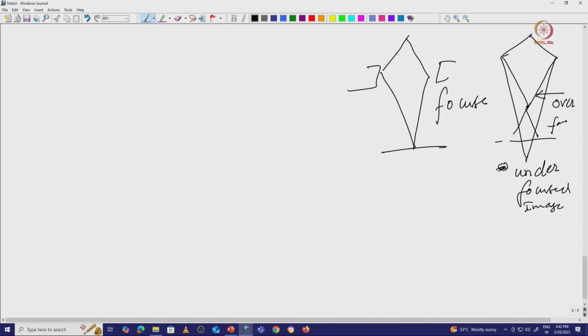So let us see, if we are using a different magnetic field, how it is going to affect. Whenever I talk about focusing the electron beam, especially after interacting with the sample, how it is focusing and how we are getting the first image in the back focal plane. The back focal plane is the plane where we are getting the diffraction pattern. In the back focal plane the electron beams are merged, so it may be focused, under focused or over focused. The three things are there.